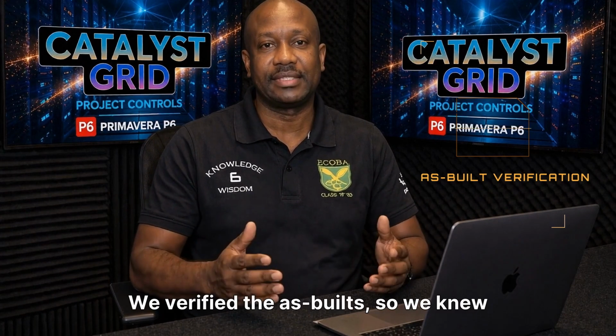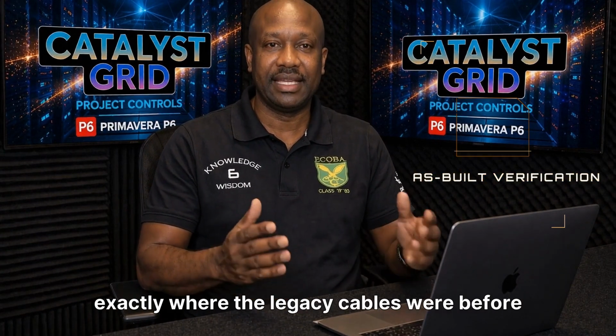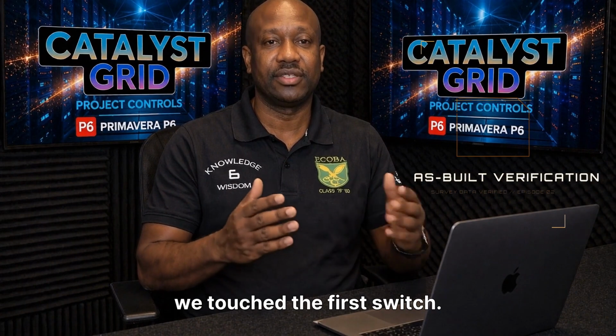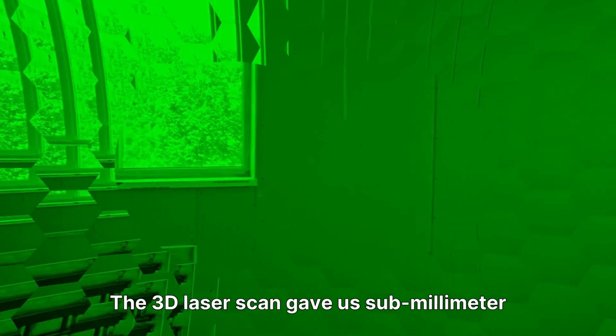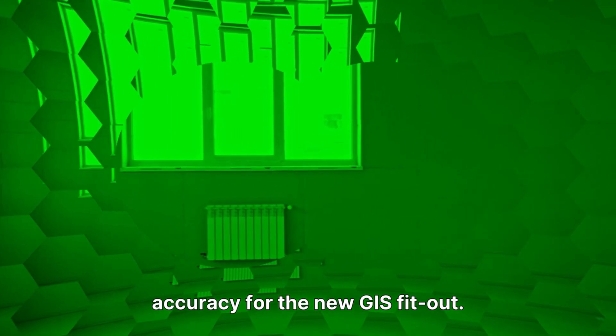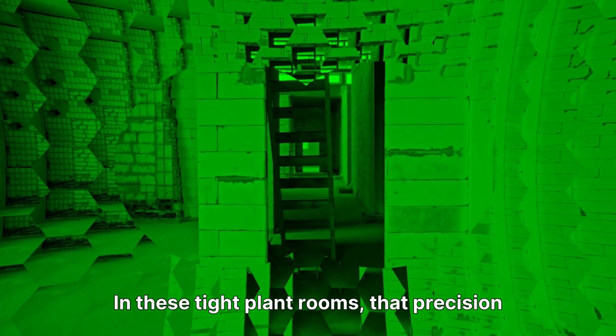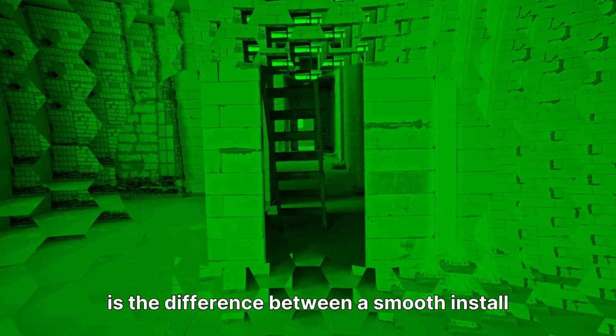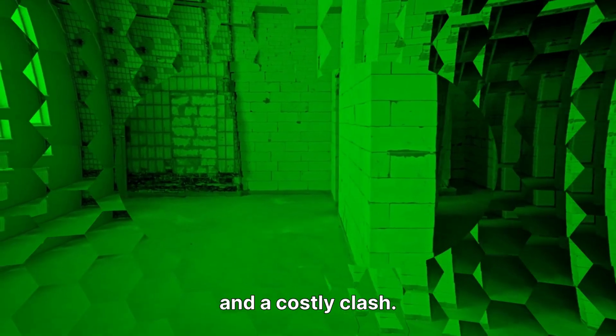We verified the as-builts, so we knew exactly where the legacy cables were before we touched the first switch. The 3D laser scan gave us sub-millimeter accuracy for the new GIS fit-out. In these tight plant rooms, that precision is the difference between a smooth install and a costly clash.